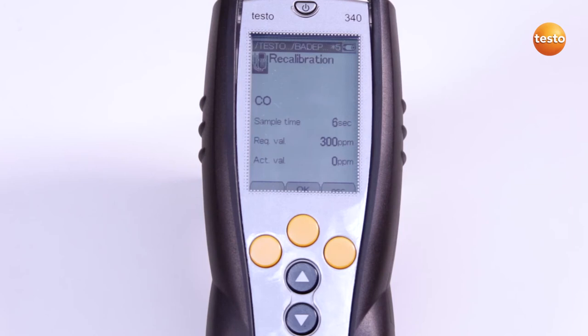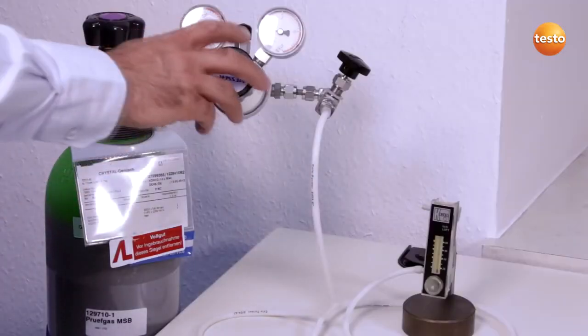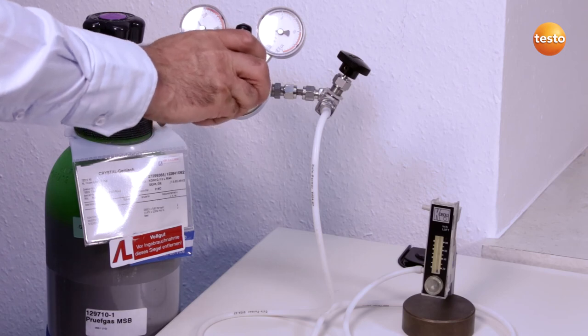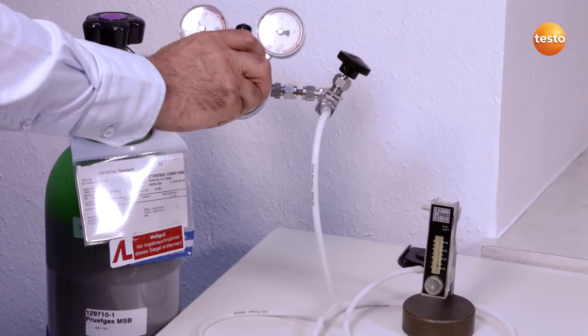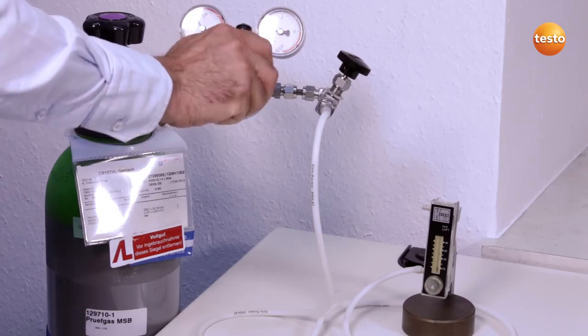The test gas is admitted via the probe tip. Alternatively, the service adapter can also be used. The sensor is now supplied with test gas for 3 minutes. For this, I open the test gas bottle and apply the gas pressureless via a bypass.